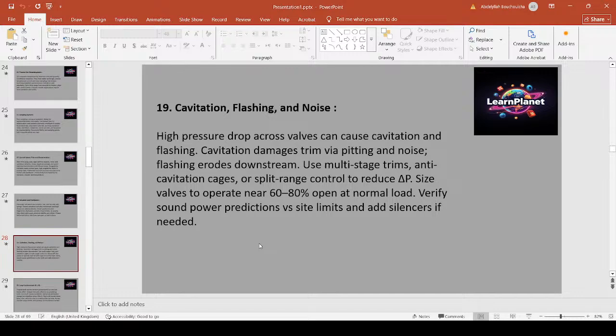Cavitation, flashing, and noise. High pressure drop across valves can cause cavitation and flashing. Cavitation damages trim via pitting and noise. Flashing erodes downstream. Use multi-stage trims, anti-cavitation cages, or split range control to reduce delta P. Size valves to operate near 60 to 80% open at normal load. Verify sound power predictions, SPL, and site limits, and add silencers if needed.